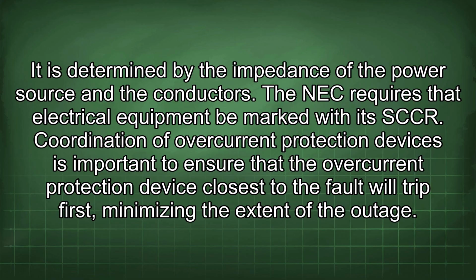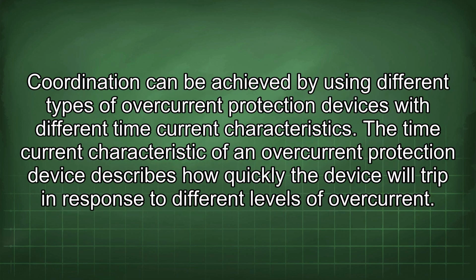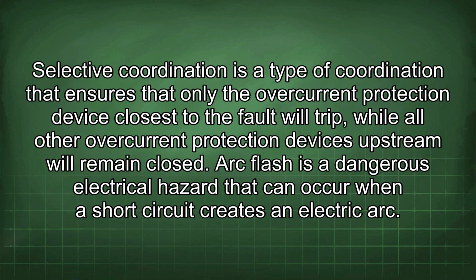Coordination of overcurrent protection devices is important to ensure that the overcurrent protection device closest to the fault will trip first, minimizing the extent of the outage. Coordination can be achieved by using different types of overcurrent protection devices with different time current characteristics. The time current characteristic of an overcurrent protection device describes how quickly the device will trip in response to different levels of overcurrent. Selective coordination is a type of coordination that ensures that only the overcurrent protection device closest to the fault will trip, while all other overcurrent protection devices upstream will remain closed.